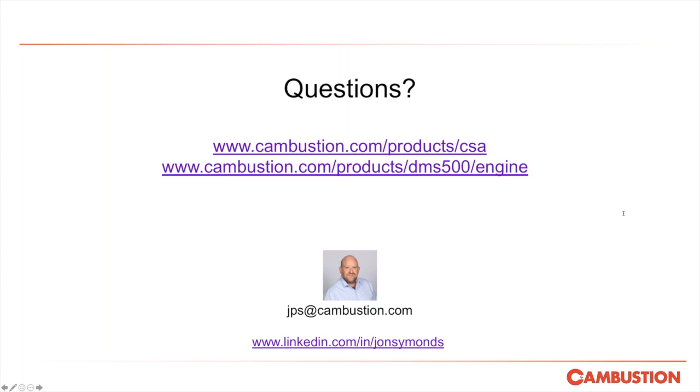And we've had a question about EU7 and test mode, so E and possibly CN7. So the current plan for EU7, as far as we know, is to have a 10 nanometer size cut. They're still in some discussion, although it's getting more and more set in the legislation. So the idea with that legislation is you would simply select the 10 nanometer size cut on the DMS software if that legislation comes in.